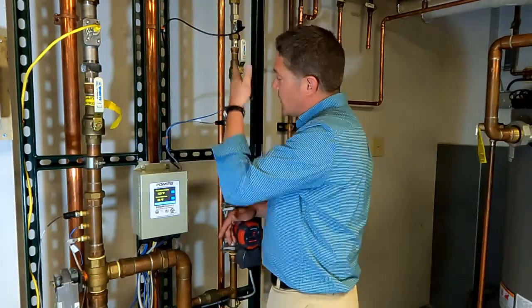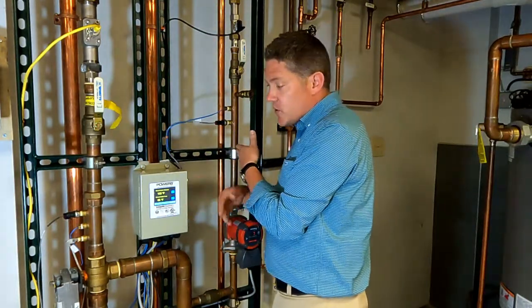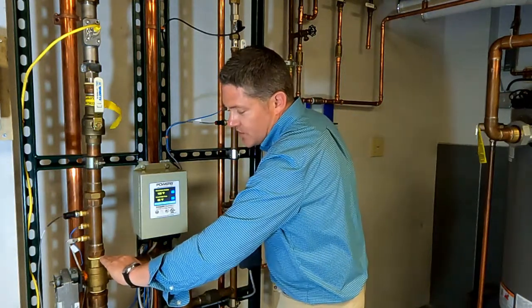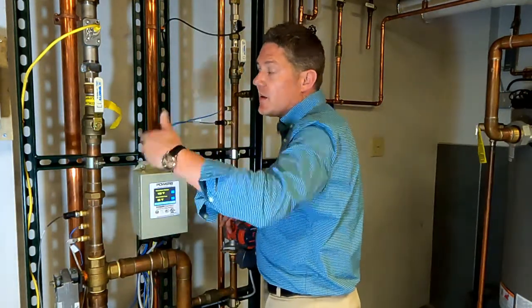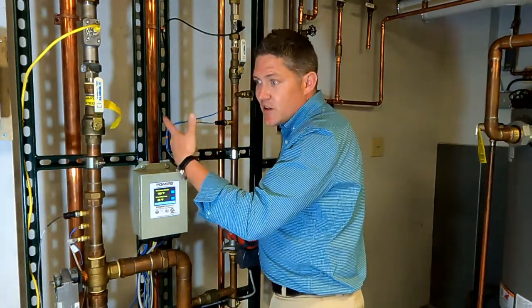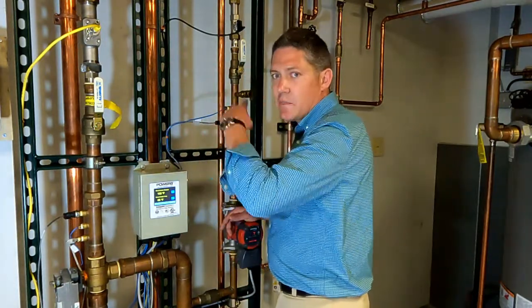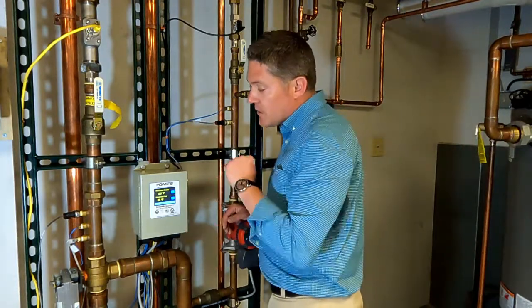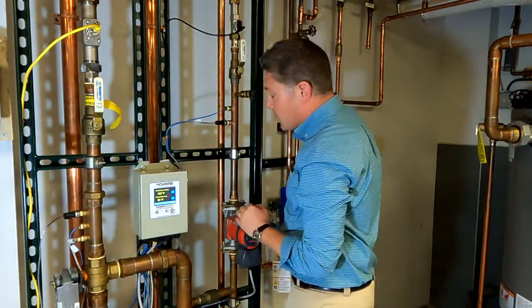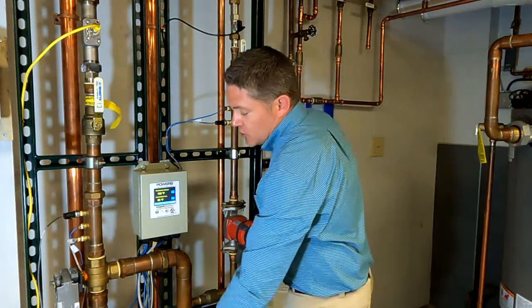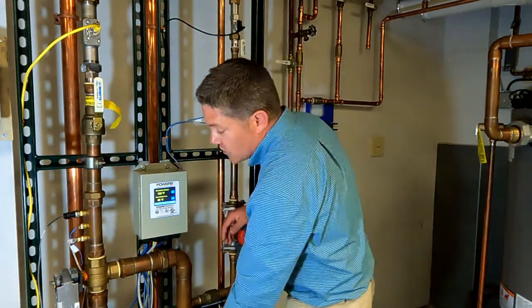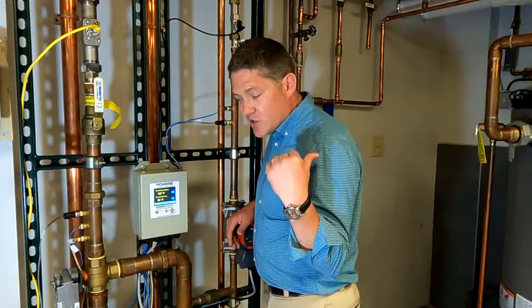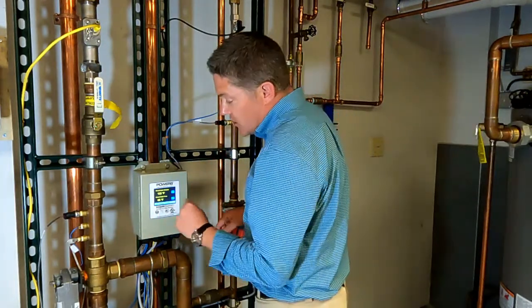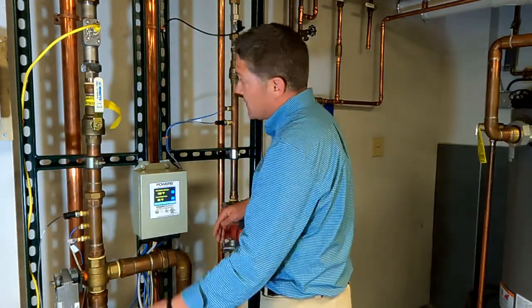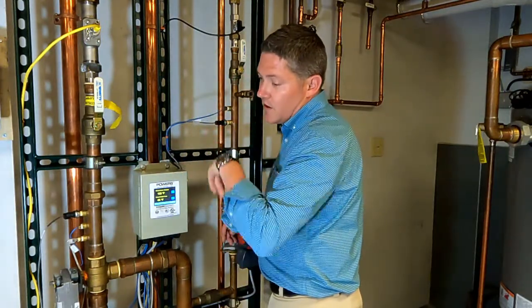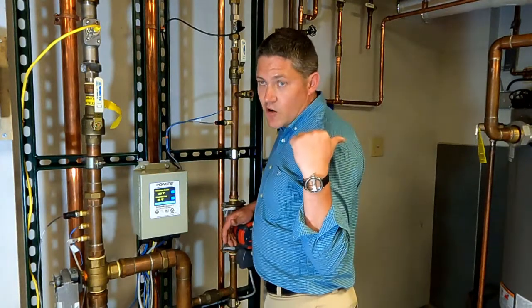let's say it went out at 120, when it got back, let's say it was at 110, so we had 10 degrees of temperature loss. If it just went right back into the valve and back out again, then it would go back out at 110, and we lose another 10 degrees on that loop, come back at 100, and it would keep dropping like that until you hit the ambient temperature of the building. If all that return water went right back to the water heater, then there's no way to push new cold water in to blend with it, so it would just be pushing out the supplied hot water in storage. Let's say at 160 degrees, you would see the temperature creep up until all the water in the return loop was at whatever temperature the water heater is at.